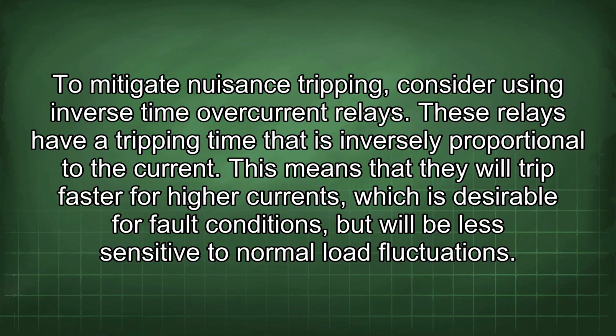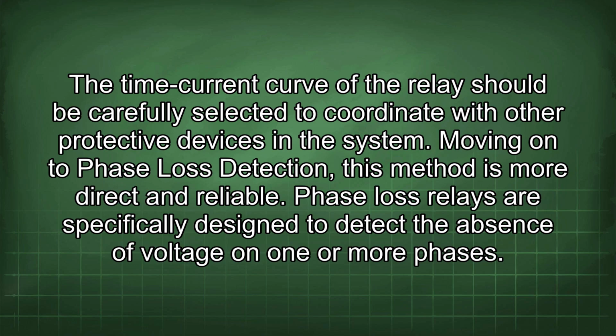To mitigate nuisance tripping, consider using inverse time overcurrent relays. These relays have a tripping time that is inversely proportional to the current. This means that they will trip faster for higher currents, which is desirable for fault conditions, but will be less sensitive to normal load fluctuations. The time current curve of the relay should be carefully selected to coordinate with other protective devices in the system.